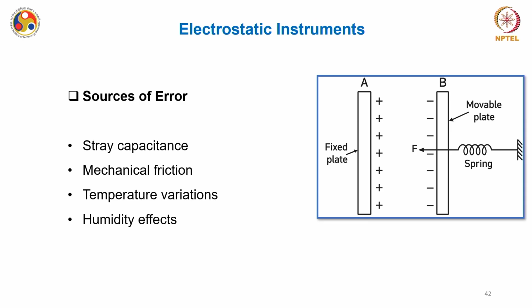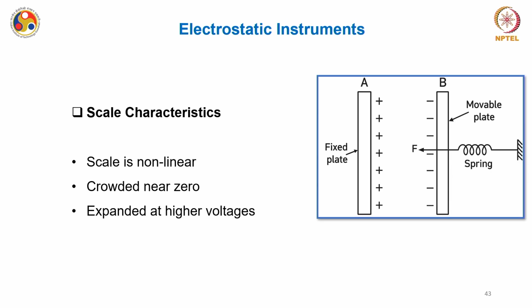The sources of errors in these electrostatic instruments can be various, including extra stray capacitances in the instrument. Mechanical friction can lead to erroneous results in the measurement. Temperature variation is one of the major factors because of which you see erroneous results on an electrostatic instrument. They also suffer from ambient conditions like humidity and other things. So you should have provisions to control all these things in an electrostatic instrument. This instrument has a non-linear scale because the deflection is directly proportional to V square, as we have seen from equation 11. So when you have this non-linear scale, theta is directly proportional to V square, which means that the scale at the lower readings is very crowded. And in the end you have an expanded scale or measurement marks on the higher side of potential.